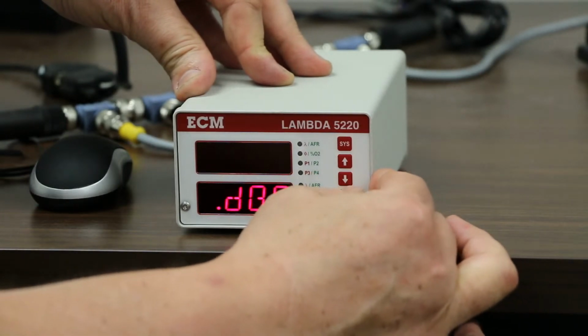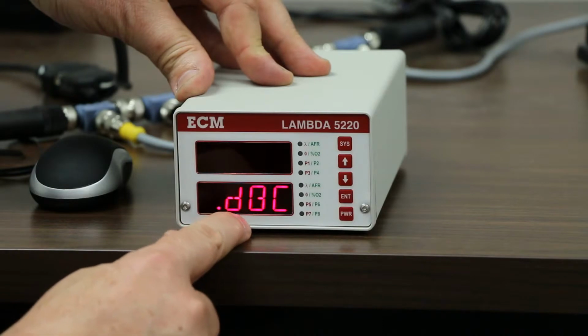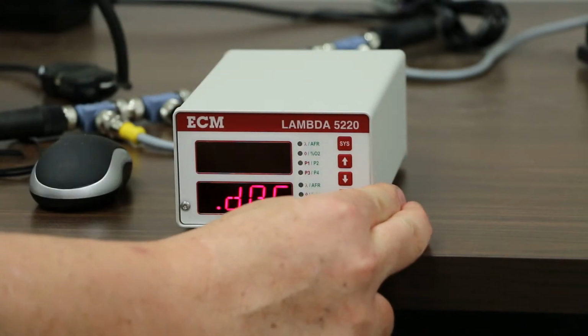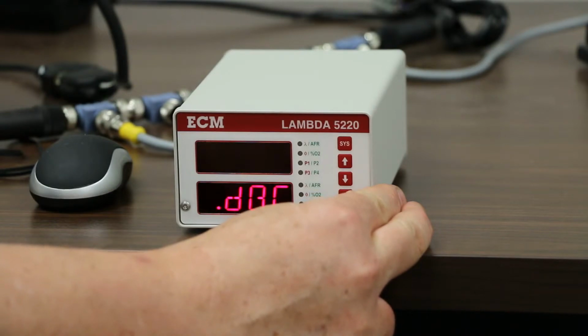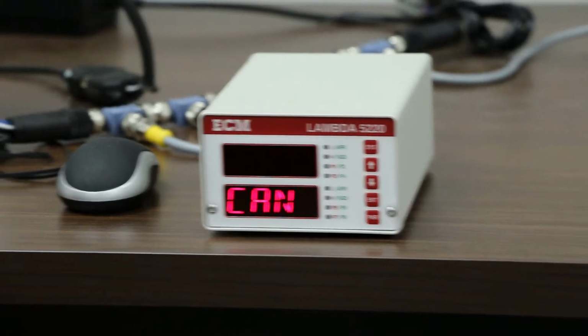Then click once more, and you go to this .dbc setting. With this display showing Please configure CAN outputs, you press enter, you get the rolling wheel, and the information that's going to be used to produce a .dbc file for these parameters is now uploaded to the software.